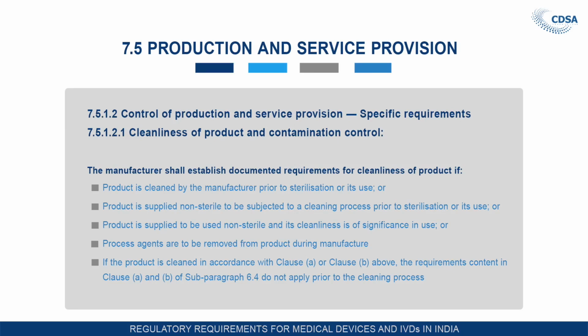Control of production and service provision, specific requirements. 7.5.1.2 is the control, and point 1 of this control is cleanliness of product and contamination control. The manufacturer shall establish documented requirements for cleanliness of the product if the product is cleaned by the manufacturer prior to sterilization or its use, or the product is supplied non-sterile to be subjected to a cleaning process prior to sterilization or its use, or the product is supplied to be used non-sterile and its cleanliness is of significance in use, or the process agents are to be removed from the product during manufacture.